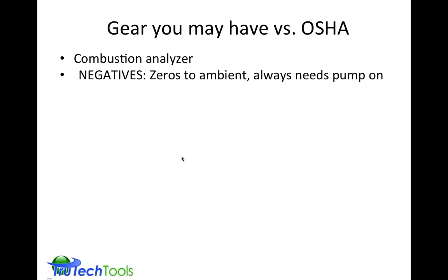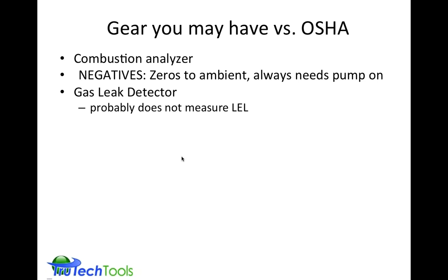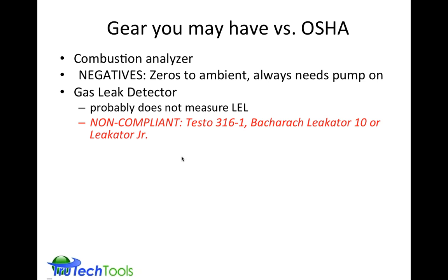You would always need to have the pump on because the sensors are not exposed and external like a lot of the personal monitors are. For the gas leak detection part of OSHA, where you have to be aware of the physical hazard of an explosive gas, you probably are not able to measure LEL unless you have one of just a couple different LEL meters that we will talk about. So things like a Testo 316, again, not brand bashing here, Bacharach Leakator 10, Leakator Junior, do not measure LEL. That's just a fact. So they're not going to be a good gas leak detector to tell you how close you are to a dangerous condition. They'll tell you that a leak is present, but not how much.